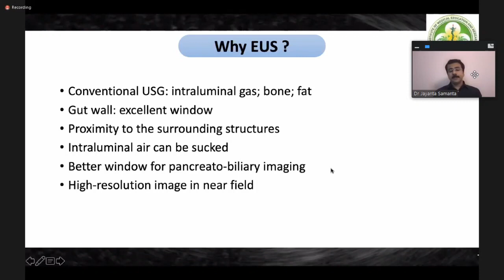In those situations, if we place the transducer inside the gut lumen, it gets very closely proximate to the gut wall, and hence it enables us to get a better picture of the immediate surrounding structures of the gut wall. Another advantage of EUS is that it has a suction port, so we can suck out the air, which is one of the major hindrances to getting a very good image on a conventional ultrasound. So it gives a very good window for pancreatobiliary imaging. In fact, EUS is one of the most accurate imaging modalities for pancreatobiliary imaging, over and above the other imaging modalities available. And it gives a very high resolution image because it is very close to the field where we want to get the image.